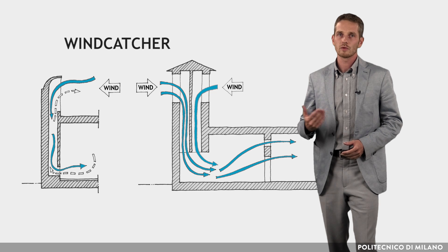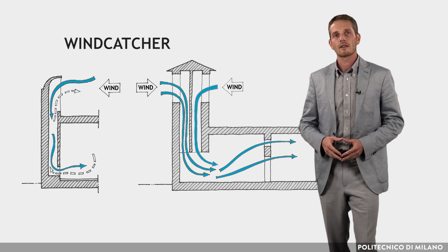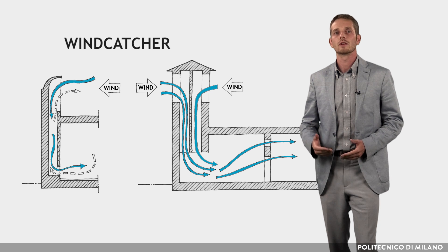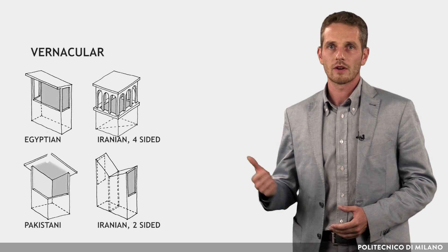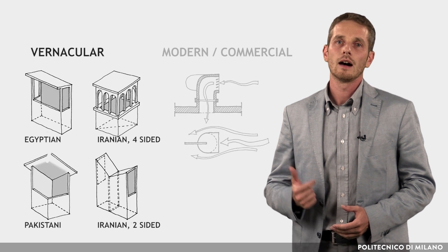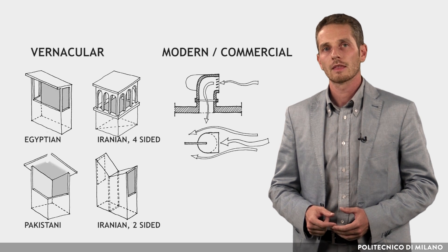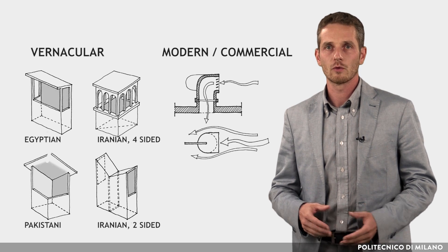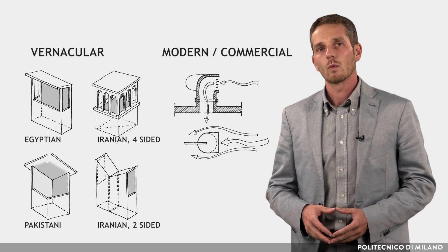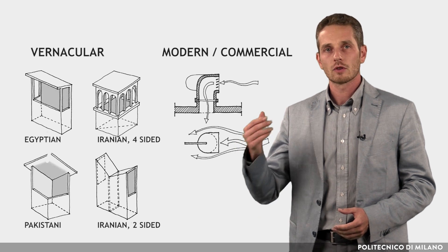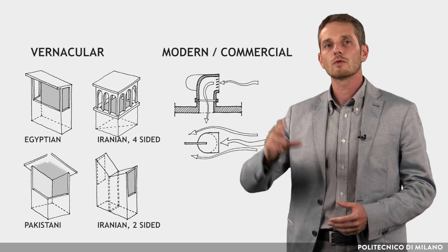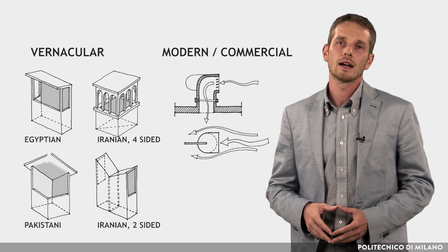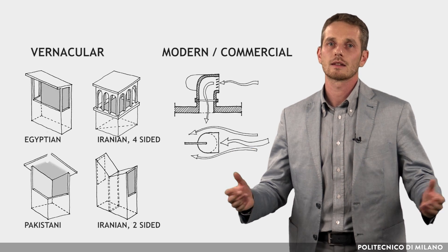A prerequisite for using a wind catcher is that the site should experience winds with fairly good consistent speed. Wind catchers can be categorized in two groups: vernacular wind catchers and modern or commercial ones. The foundation of these types of wind catchers is almost the same. Wind catcher inlets, in order to rise above the layer of turbulence and drag, should be at least 2.4 meters above the height of the surrounding buildings and obstructions.